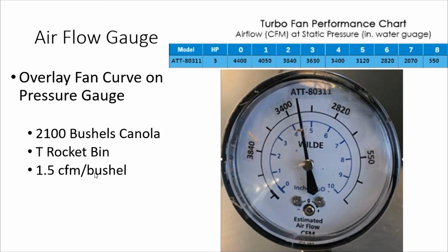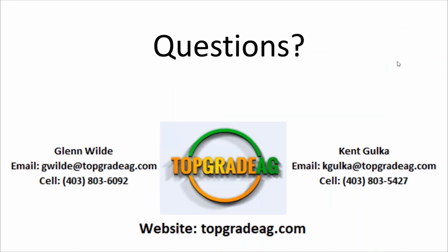So you can just see how this really is a valuable tool, not only for knowing your airflow, but more importantly, knowing if your fan is the right fan for you. In many instances, when you put these gauges on your low speed centrifugal fans, you really get an eye opener because they just can't push against the higher pressures. So that summarizes the presentation, and if there are any questions, I'd be happy to address them.